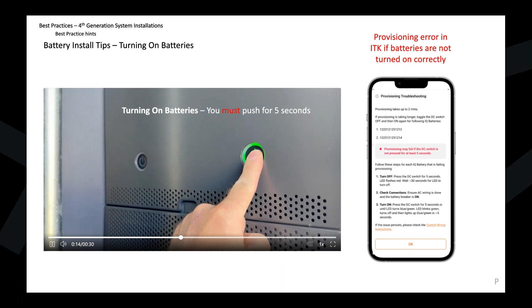When we power on the batteries, you're going to press and hold that battery button for 5 full seconds, like 5 schoolyard Mississippis. Then you'll see the light start to flash, but you have to hold it in for the full 5 seconds. That's the thing a lot of people miss. They're used to our previous generation batteries where you just press the disconnect button once and it lights up. This one you have to press and hold for 5 seconds, and then the battery will start its boot up sequence with various flashing red and green lights. That's the first thing to think about: press and hold for 5 full Mississippis.